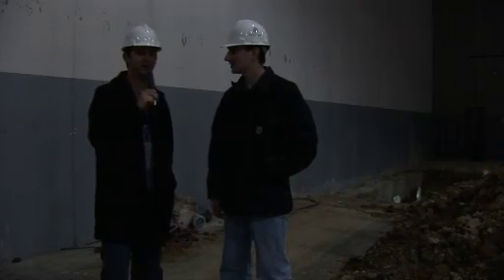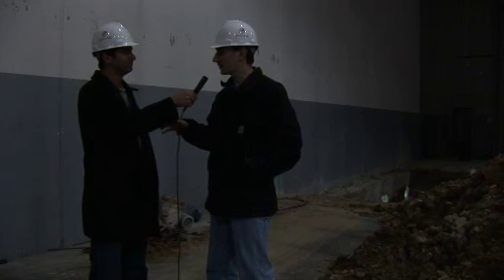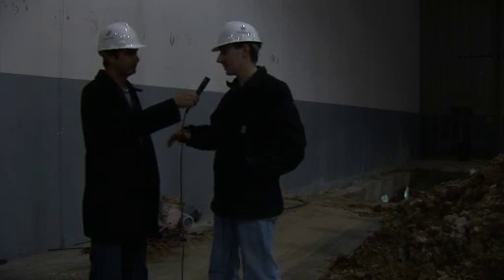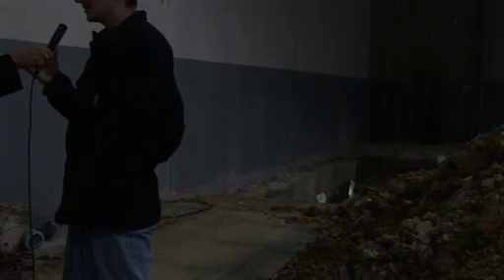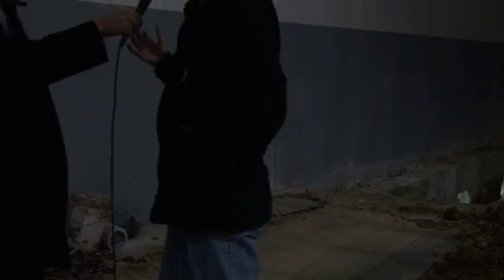Chris, earlier you were telling me about some pretty fancy equipment that's going in here. Can you tell me a little bit more about it? Right in this room here, we're going to have our incoming electrical service equipment. Right behind us, we have excavated out so that we'll be able to fit all of our underground cable in here. We're going to start off with some ASCO 7000 series automatic transfer switches, and from there, we're going to go to some distribution switch gear and then to our UPS units and air conditioning and so on. Within, say, a week and a half, we should finish getting all this conduit in here, get all the concrete poured back in, and be ready to set that equipment. It's showing up any day now.